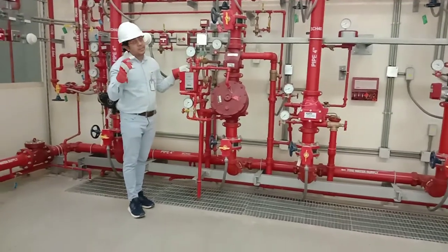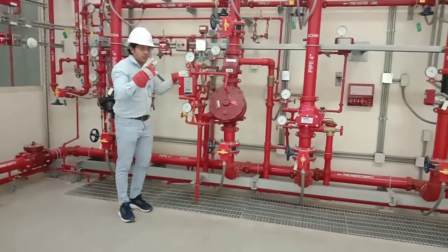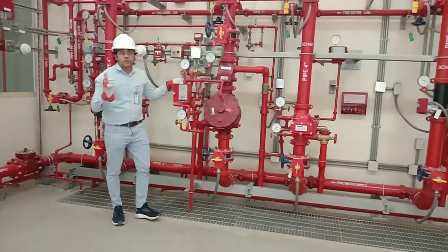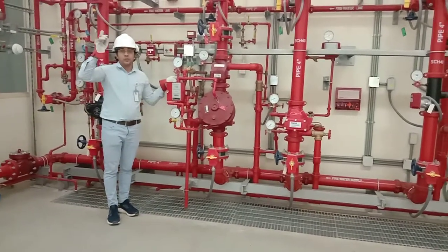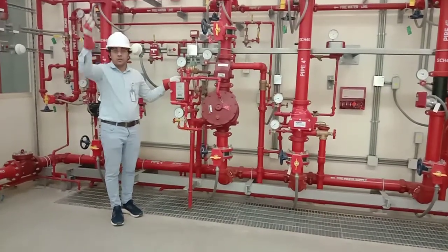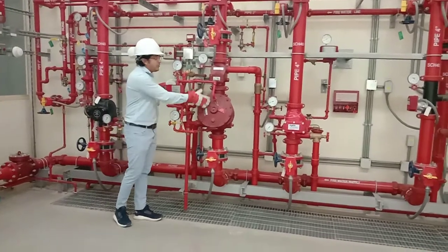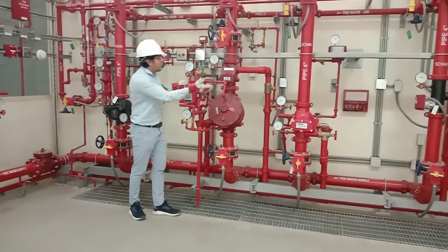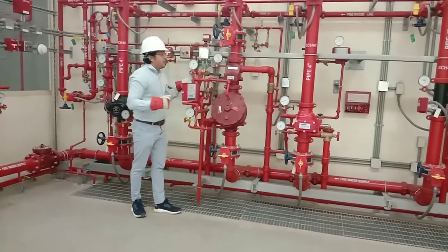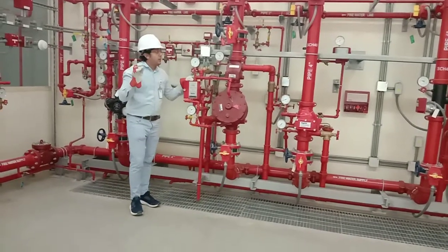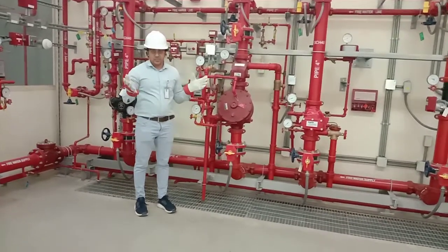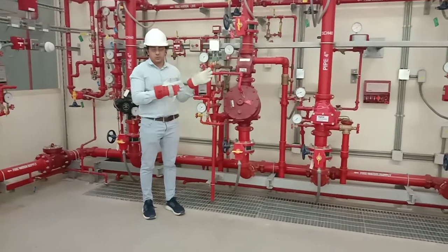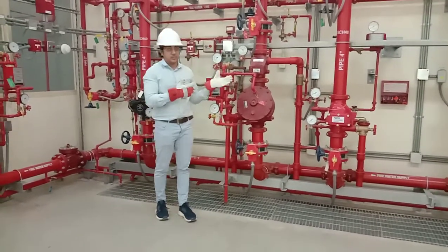We need two detections to allow water to go inside the system. The first one, the sprinkler system needs to be fused, right, and then air should go out. At that time, due to the difference in the pressure, the valve will open and water will go inside. But at the same time, suppose your sprinkler system breaks by mistake, right? Water should not go inside because this is protected.